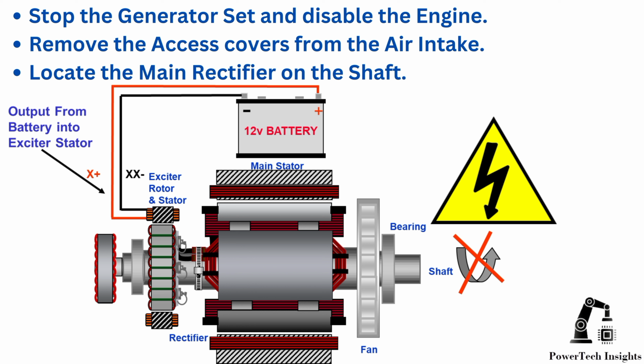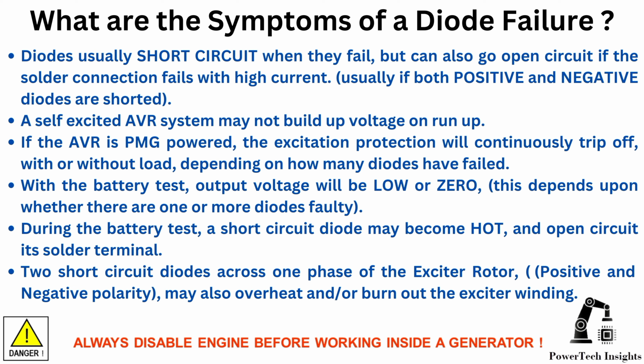Follow lockout-tagout, LOTO procedure. Remove the access covers from the air intake. Locate the main rectifier on the shaft. Possible symptoms of a diode failure: diodes usually short circuit when they fail, but can also go open circuit if the solder connection fails with high current, usually if both positive and negative diodes are shorted.